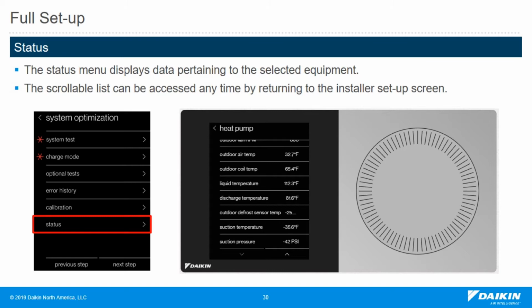At any point, if you're having issues and you do not have a D-checker and you do not have a laptop connected to the equipment recording, you can do some screenshots of this screen. This is not a live screen. When you go to status, it's going to pull the data in and report it on a screen. If you have a time period which went by, you might want to leave this screen, go back and re-enter status to get some updated numbers.